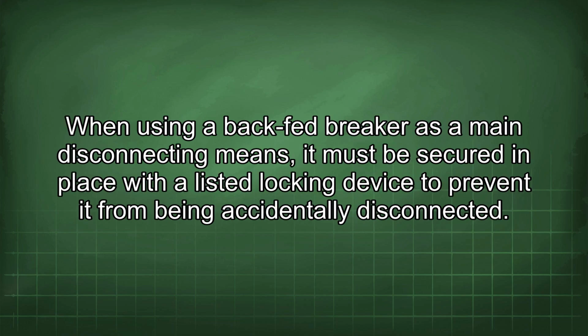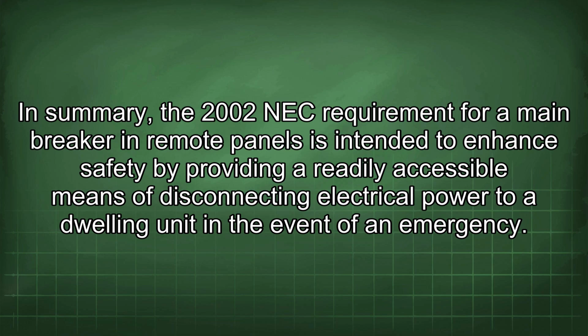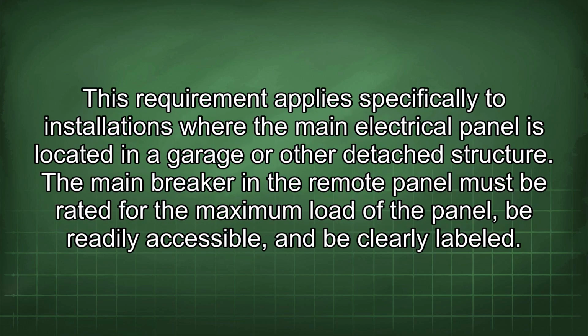When using a back-fed breaker as a main disconnecting means, it must be secured in place with a listed locking device to prevent it from being accidentally disconnected. In summary, the 2002 NEC requirement for a main breaker in remote panels is intended to enhance safety by providing a readily accessible means of disconnecting electrical power to a dwelling unit in the event of an emergency. This requirement applies specifically to installations where the main electrical panel is located in a garage or other detached structure.